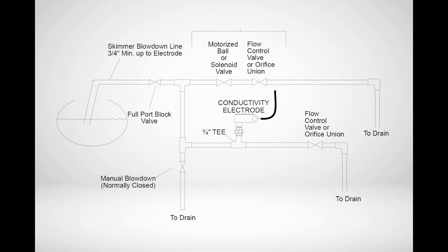Very large boilers may be plumbed with a small continuous blowdown that passes the conductivity sensor. When the conductivity reading increases above the set point, a valve in a second larger line will be directed to open on a larger blowdown line. For these installations, the relay wired to the blowdown valve only needs to be programmed with a simple on-off set point with a dead band.